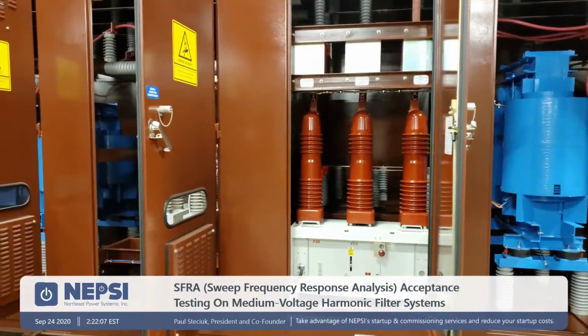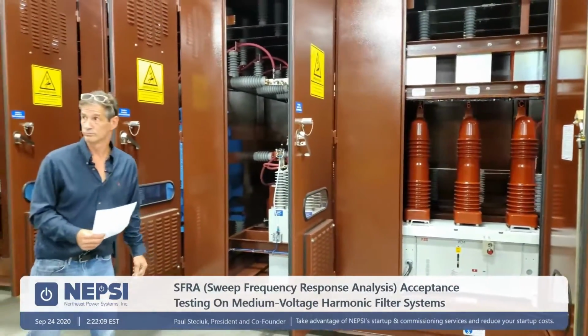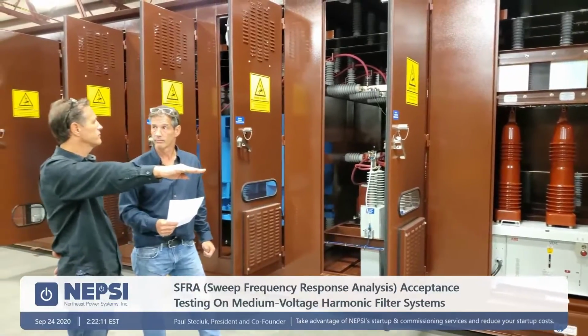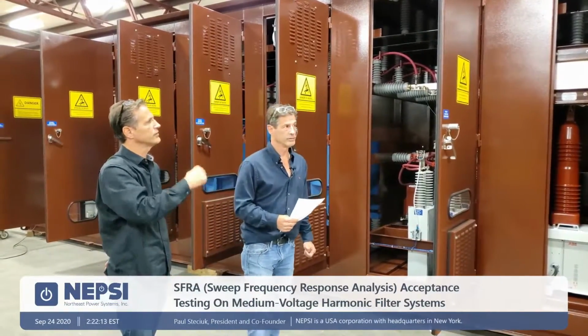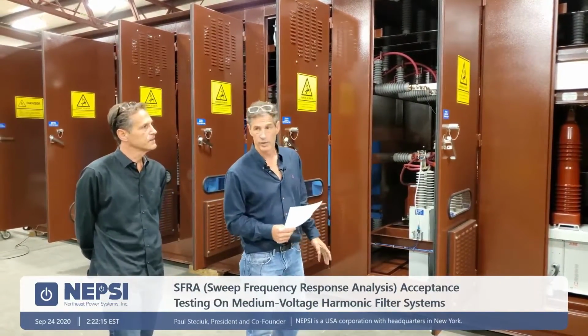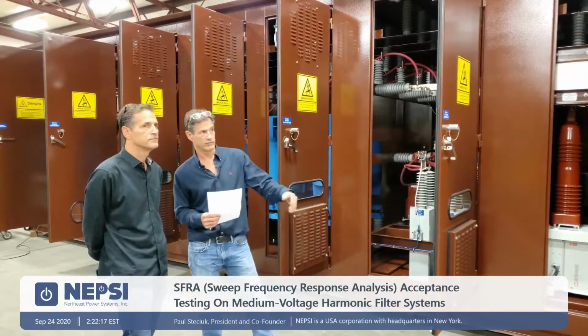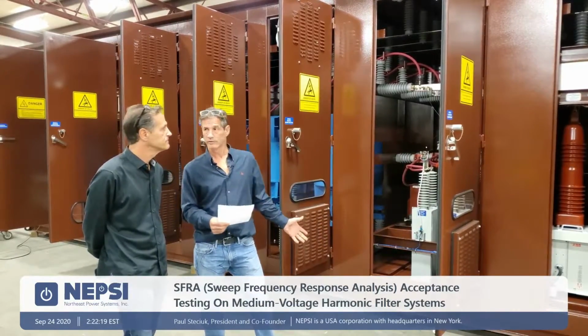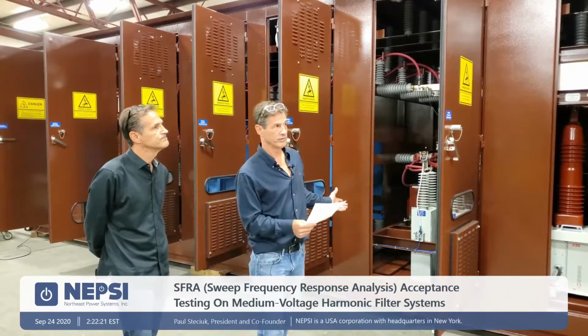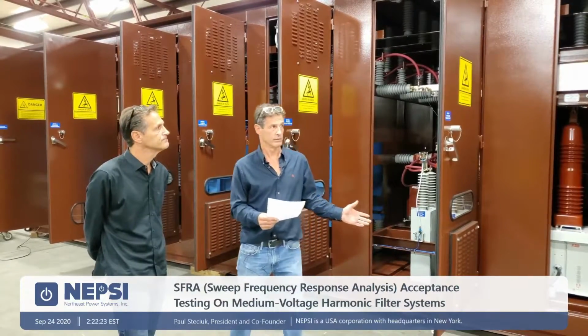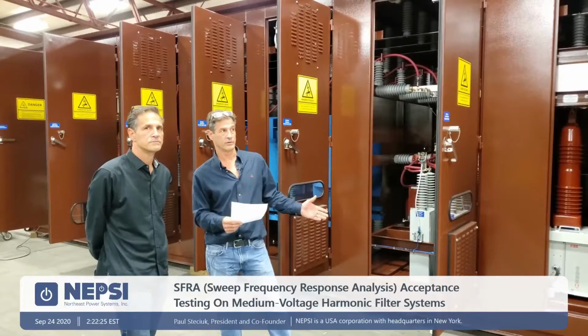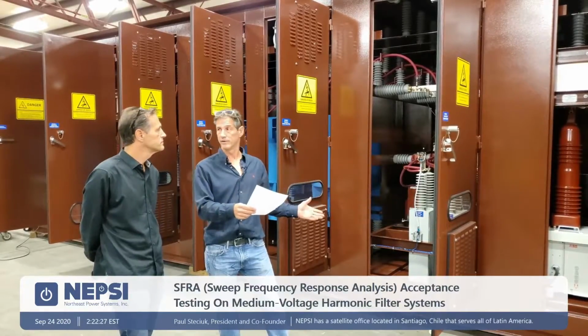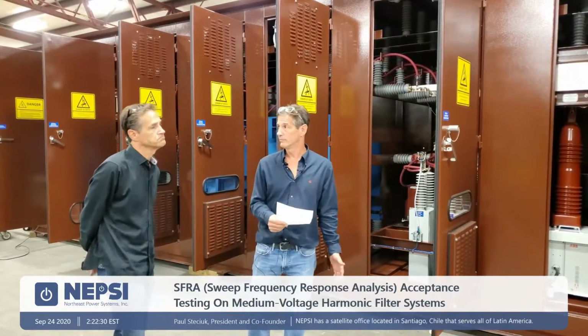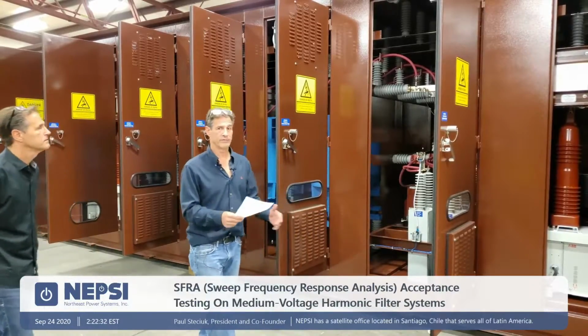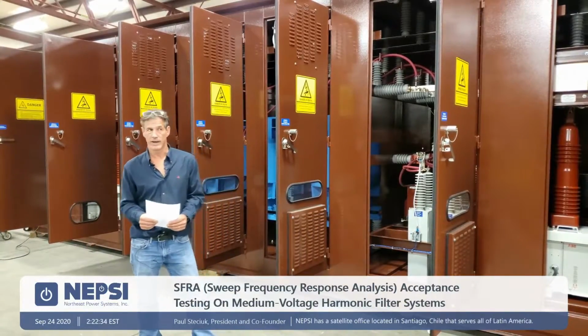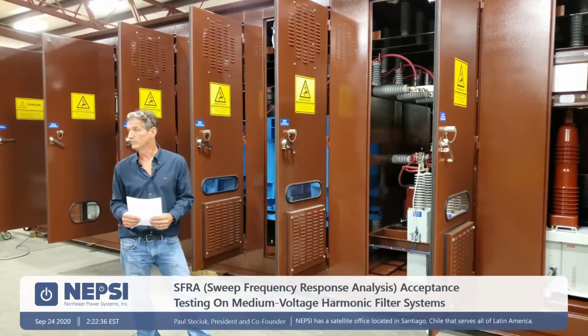So Pete, maybe I ask a question. So you do the test with everything closed? Is that the way you typically do it, or do you do it with the stage open? We can do it either way, but we typically close all the stages because if we run into an issue where we see an anomaly between the phases, between each stage, we'll then maybe open the stage to try to isolate where the problem is. But we normally do a test. If everything looks proper in the scan, we won't have to open each stage individually.